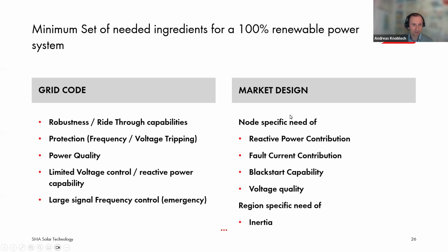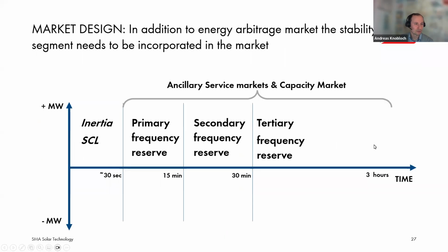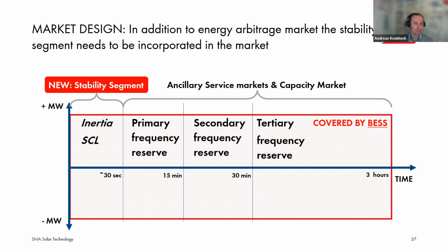Market design would be appropriate if there would be a node-specific need and market creation for reactive power contribution, fault current contribution, black start, voltage quality, and also inertia. And from our perspective, there are a lot of ancillary service markets and capacity markets that are working today, which includes the primary frequency reserve market, and secondary and tertiary reserve markets. What is missing and should be introduced is a new stability segment for inertia and short circuit level provision. And the good part is that all of these services can be covered by a battery energy storage system in very efficient ways. For longer duration, of course, you need another type of storage, but many problems can be solved by battery energy storage systems, and their share in power grids will increase over time.